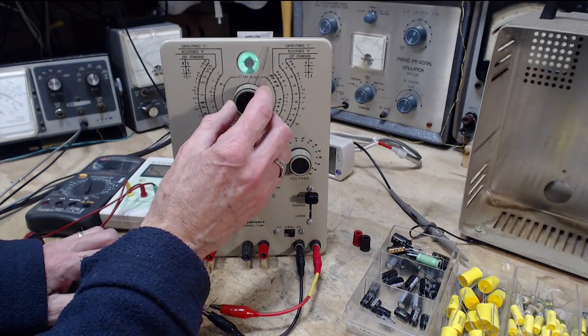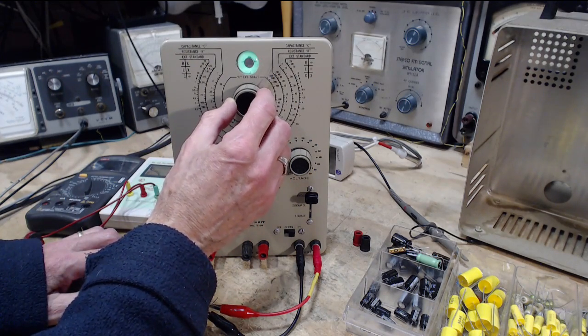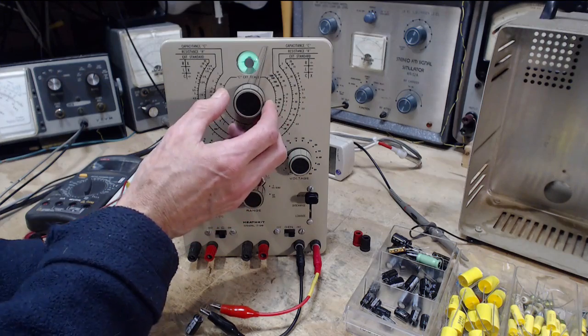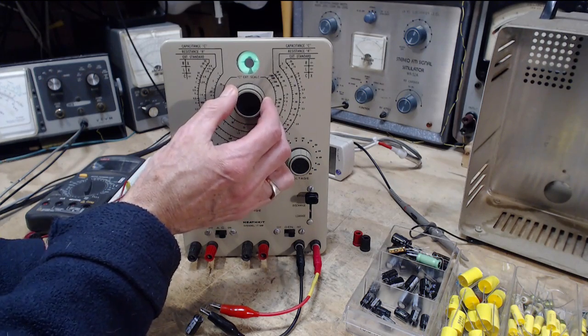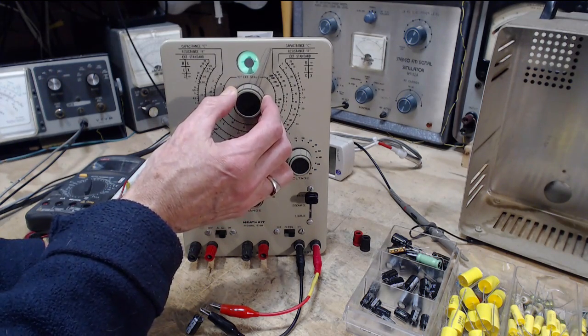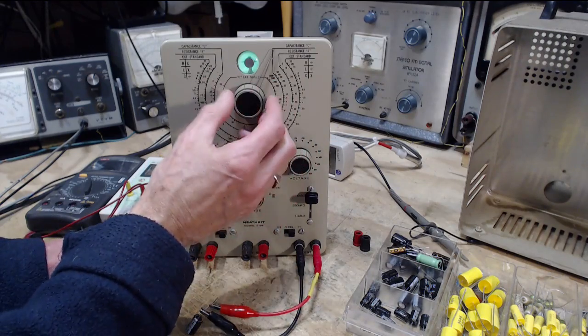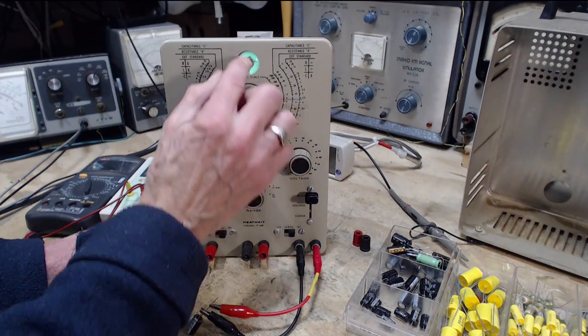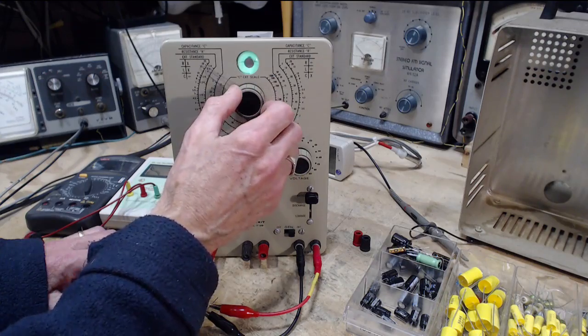It's way off. So I think I'm going to attribute this to calibration problems. When I say way off, this is not a large amount of scale up here. It's just like a lot of radios - when you get to the end of the scale, things get really crunched. So maybe a little bit of calibration to bring that down into the proper range.